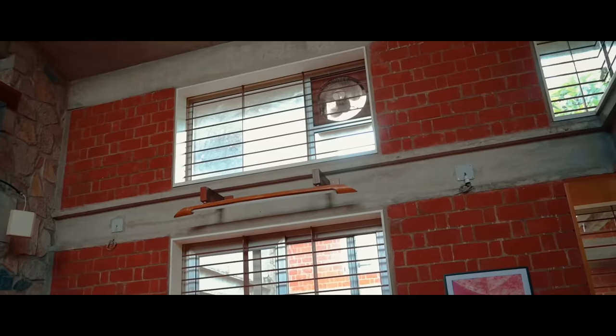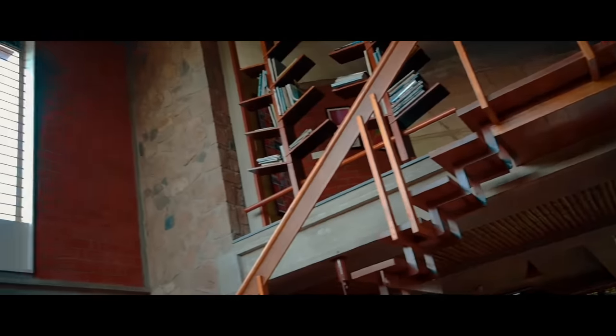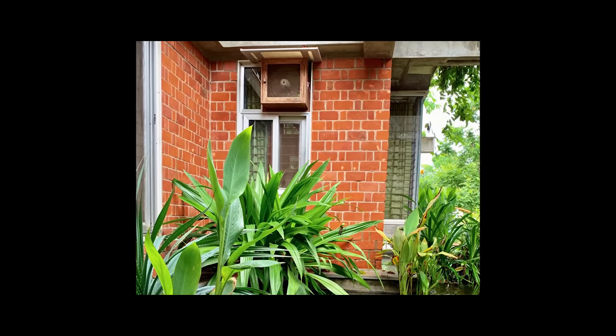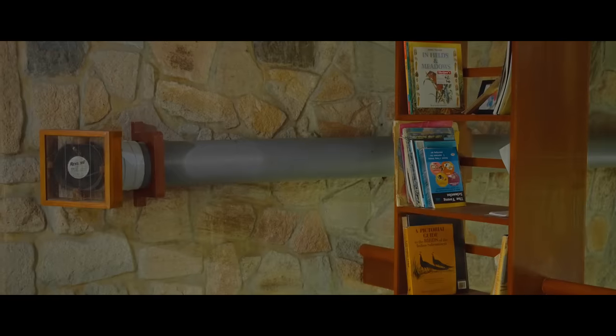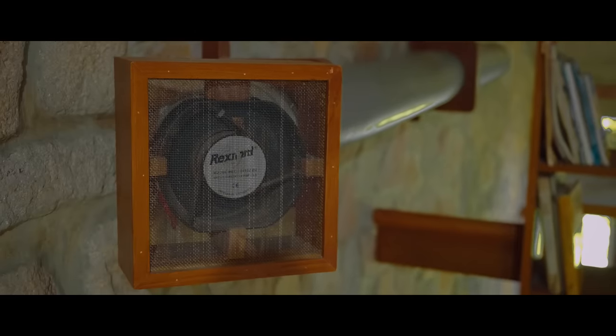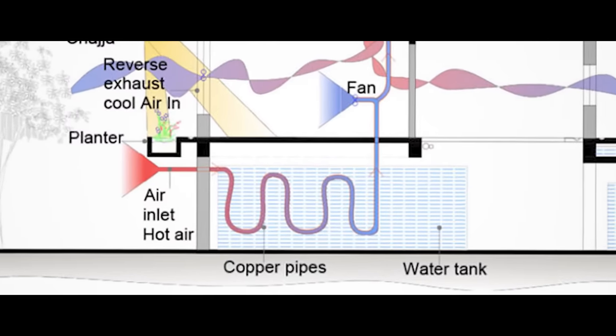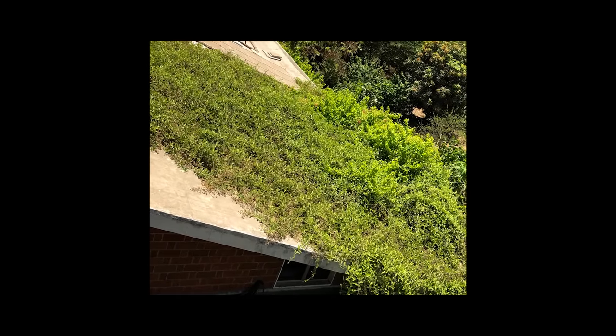The sloping roof of the house is designed so that rising hot air goes out from the top and cool air enters from the bottom. Fans are provided at low level in windows to suck in cool air from outside, and exhaust fans are provided on the top side near the roof to push hot air out. Special air cooling pipes are run through the ground floor water tank area just above the water level, with outlets in the room and a fan at the end of the pipe. Air enters the pipe at atmospheric temperature and cools down as it passes above cold water.